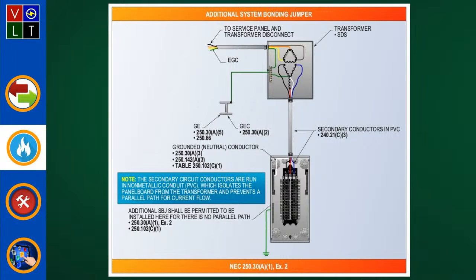So the basic rule requires a system bonding jumper and the grounding electrode conductor connection to that grounded system conductor to be made at the same point. Right. All this is an exception to the rule, but only for cases where there would not be a parallel path, such as using a non-metallic PVC conduit that's run back to the transformer source, and it's located to not share conductive contact with common structural elements or equipment grounding conductors. Right, which PVC wouldn't do anyway. That's basically what we're trying to say here.